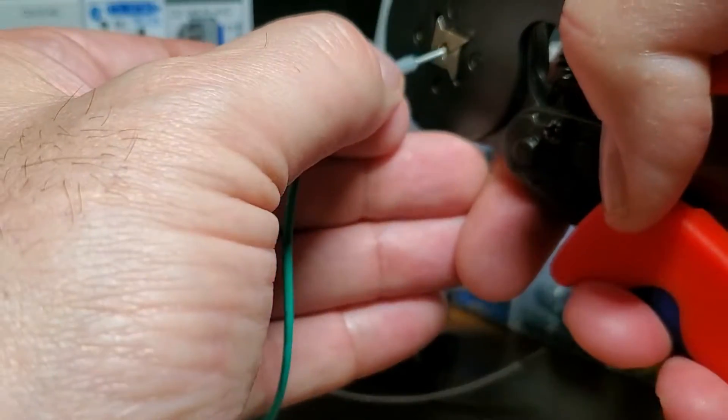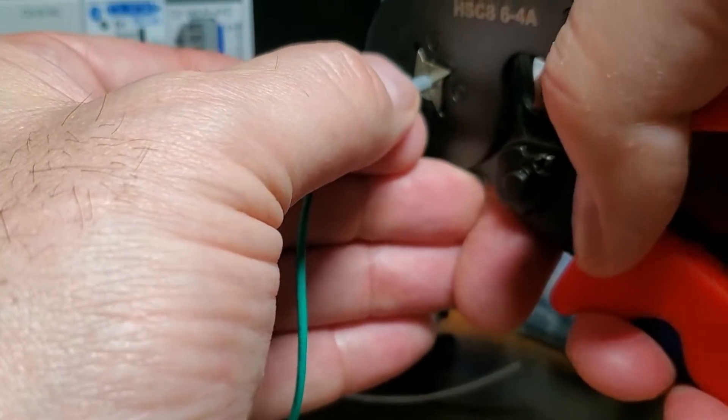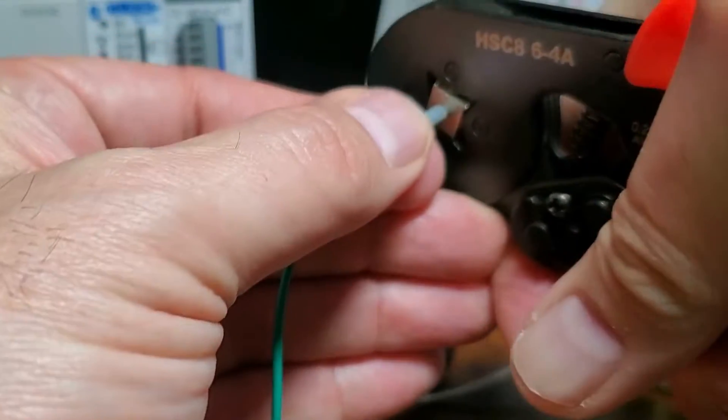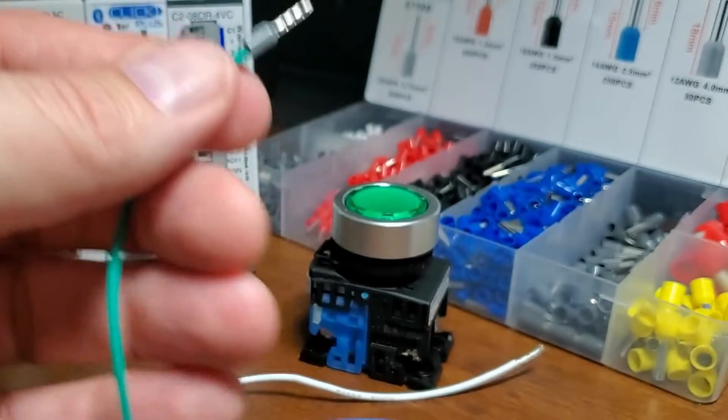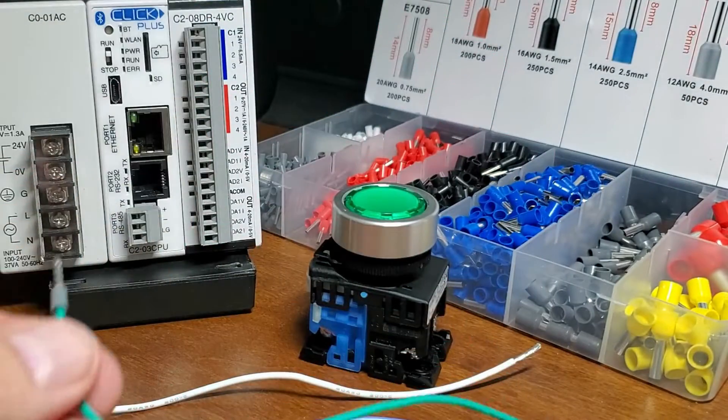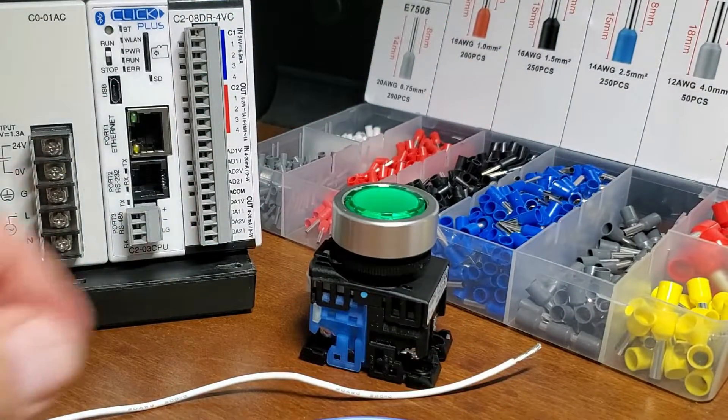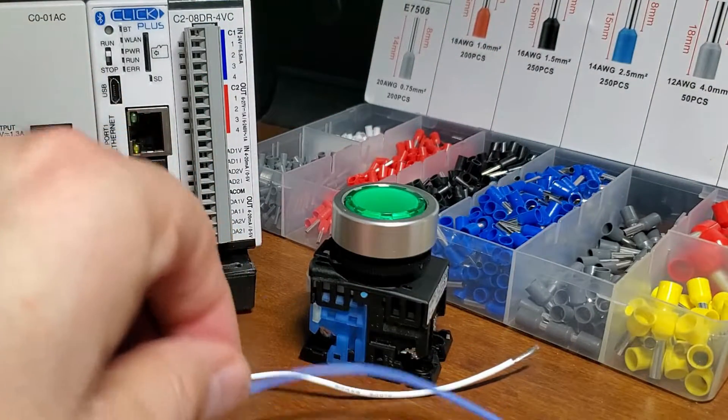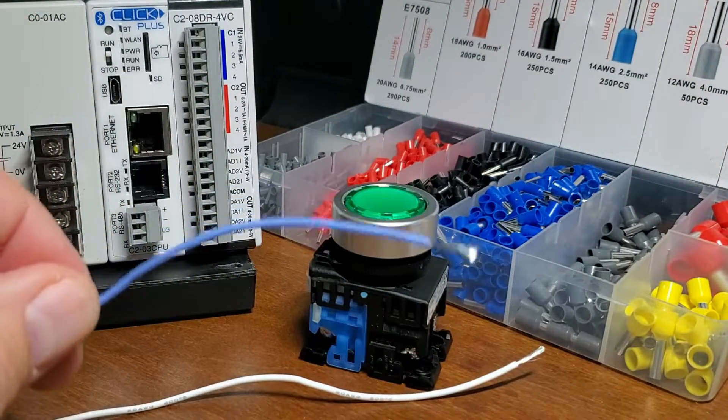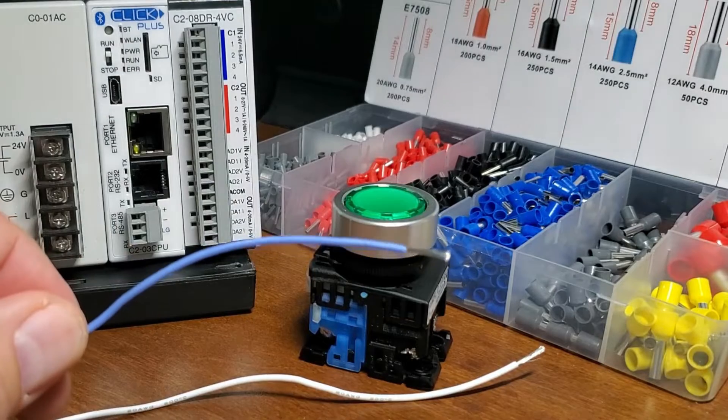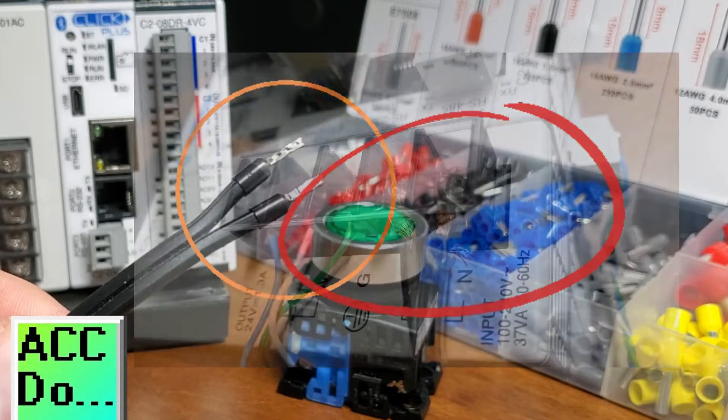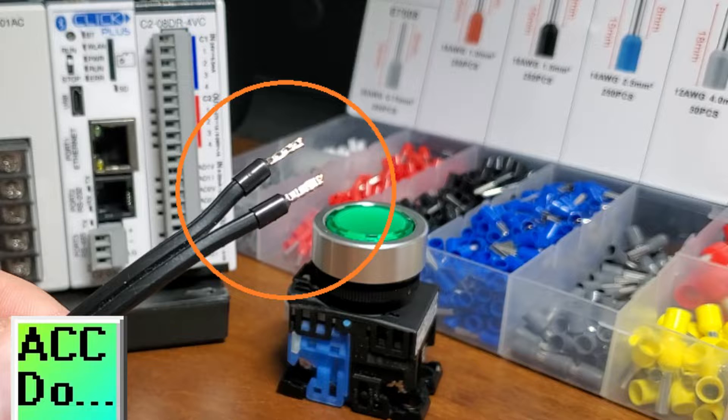A ferrule will work well with PLC, Programmable Logic Controller, terminals. Using a stranded wire directly into the terminal of the PLC is not recommended. This can cause the wire threads to bend and break, shorting out other terminal connections.